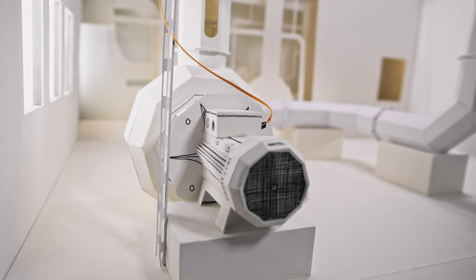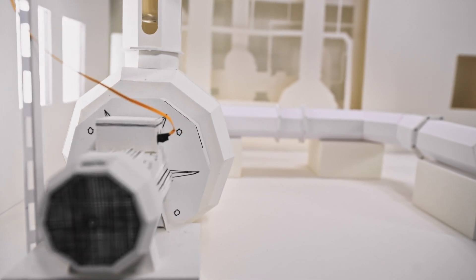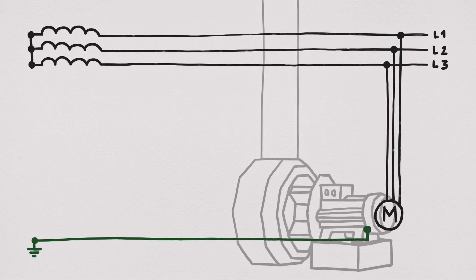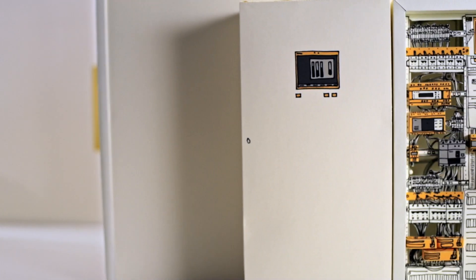But this pump is still working despite the ground fault, because it receives its electrical power via an ungrounded system. In the ungrounded system, there is no direct connection between live conductors and ground, so a ground fault which could be dangerous on a solidly grounded system does not lead to disconnection. The plant continues operating even when ground faults are present.